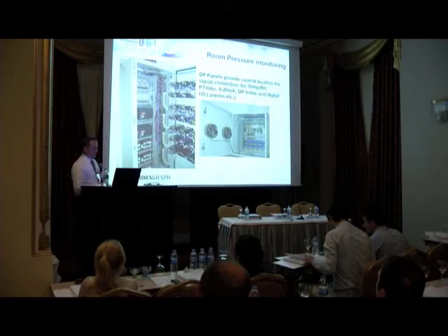So when you look at the software, typically you've got an interface menu, and you have alarm indicators which tell you whether things are good or bad. You have a control panel to turn counters on and off, or to start them, or to stop them. There is a confirmation there, and you can specify what operators are allowed to stop and start particle counters. So not everybody can just walk up and turn them on and off.